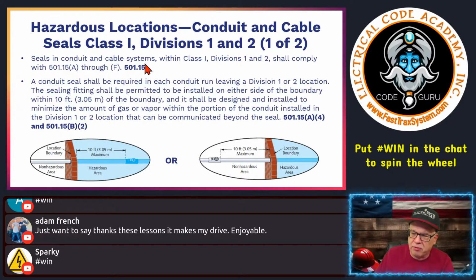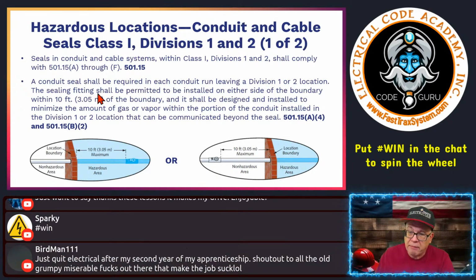Seals in conduits or cable systems, and you saw the different types of cables that we could use, within Class 1, Division 1, and Division 2 shall comply with 501.15(A) through (F). So you have an A, a B, a C, a D, an E, and F. Okay, we'll try to paraphrase this out. It says, a conduit seal shall be required in each conduit run leaving a Division 1 or Division 2 location. The seal fitting, okay, the seal fitting shall be permitted to be installed, okay.